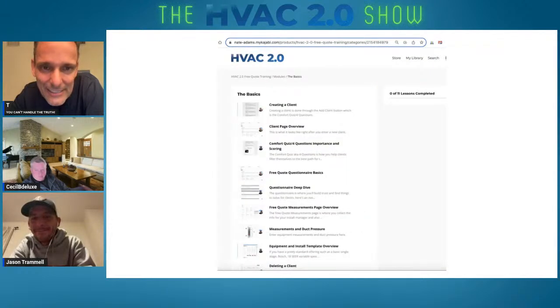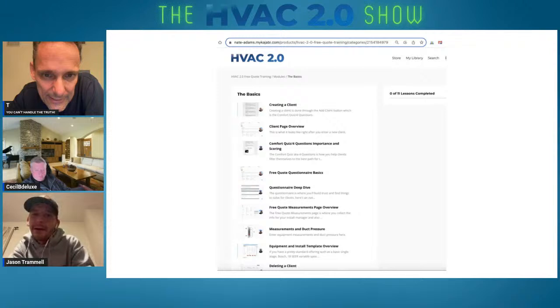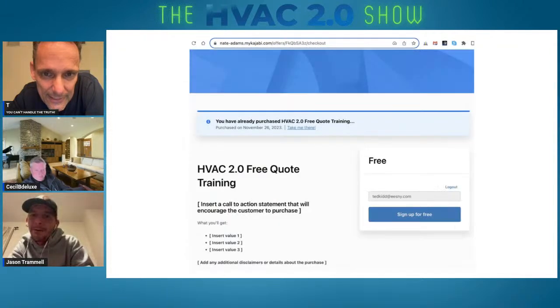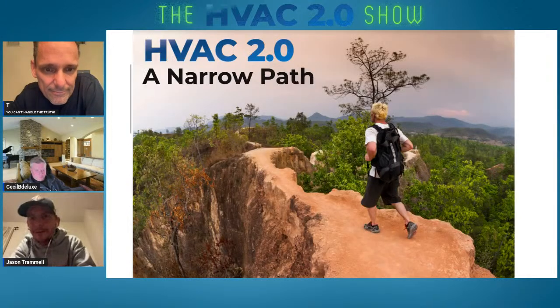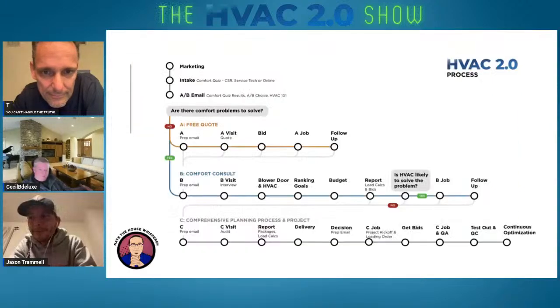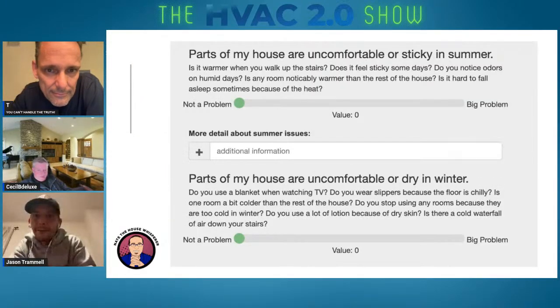There is a slide somewhere. And I can make my high end model meet the criteria, but I have to use a 5-ton indoor coil on a 3-ton unit, which, you know what that does. It makes it not dehumidify worth the crap. So then they need a whole house dehumidifier for it.